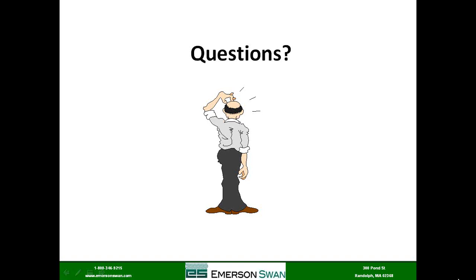Yeah, a follow-up question from Nick Sarandu about will a cast iron boiler work well with setback? I think a cast iron boiler will be fine. It's the delivery portion, how quickly they respond, that we'd be most concerned about. Right, it's the speed that the system recovers from that. Remember, you're heating the air in the building, and so you lose that many degrees. If you set it back 8 or 10 degrees, well, then you've got to recover that. And to me, it's the law of diminishing returns, that everything you saved, you put back in, plus, in getting it back up to the comfortable temperature.